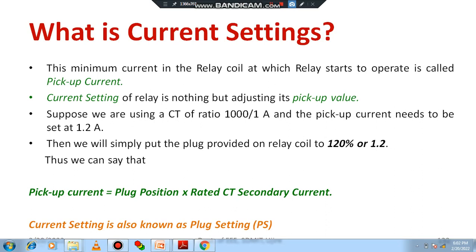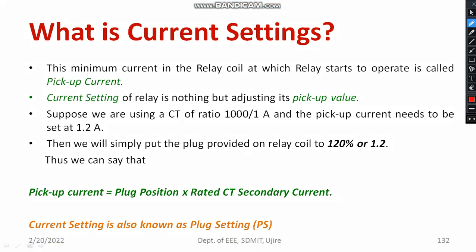So, what is current setting actually? The minimum current in the relay coil at which the relay starts operating is called pickup current, or you can call it the pickup value. After the pickup value or pickup current, the relay starts operating. Current setting of the relay is nothing but adjusting the pickup value — that is basically called current setting.